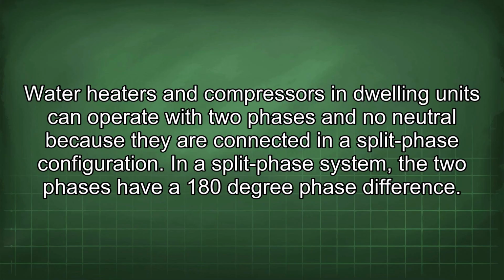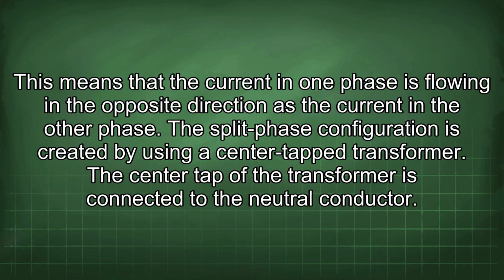Water heaters and compressors in dwelling units can operate with two phases and no neutral because they are connected in a split-phase configuration. In a split-phase system, the two phases have a 180-degree phase difference. This means that the current in one phase is flowing in the opposite direction as the current in the other phase. The split-phase configuration is created by using a center tap transformer.